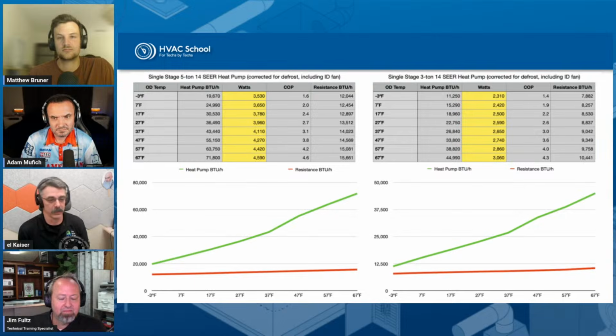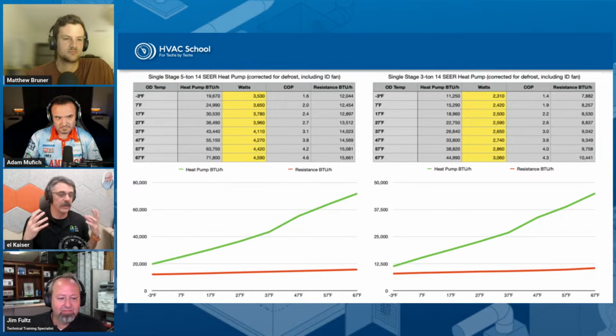And these particular units happen to have manufacturer's performance data that goes down to -3. So if we look at -3 on the 5 ton, I've got a COP of 1.6. And on the 3 ton, I've got a COP of 1.4 at -3 degrees Fahrenheit. Which tells me that even at -3 degrees Fahrenheit, I am still producing heat less expensively with that heat pump than I could by running straight electric heat. So I'm still getting more heat for my money. Now, it's probably not going to be enough to heat the house. In fact, I can almost guarantee you it's not enough to heat the house, but it can heat a portion of the house. And we'll get into that as we go on farther.